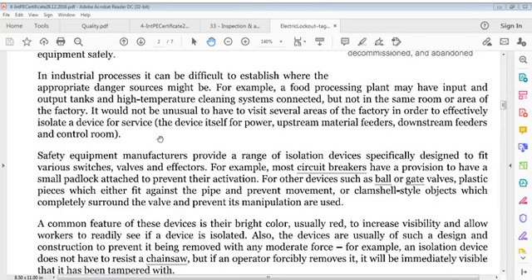In industrial processes, it can be difficult to establish where appropriate danger sources might be. For example, a food processing plant may have input and output tanks and a high temperature cleaning system connected, but not in the same room or area of the factory. It would not be unusual to have to visit several areas of the factory in order to effectively isolate a device for service: the device itself for power, upstream material feeders, downstream feeders and the control room.